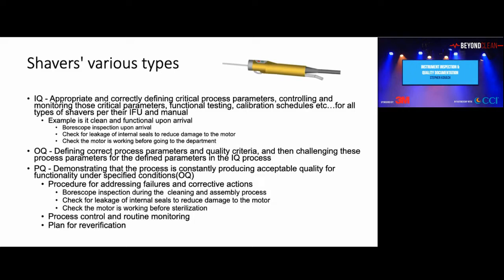You must demonstrate it. What did you use in the OQ? You might have used a flexible inspection scope, a borescope. You made sure it was working every time. So when it comes to you in assembly, you're going to look with the borescope. You're going to plug it in, make sure the motor works, make sure the seals work with different tests. You're going to put that in as your regular monitoring. You're going to document. If it doesn't work, you'll send it out or whatever. But if you do this when it comes in, you now know it works. You know what you must check for, and it must meet those requirements.